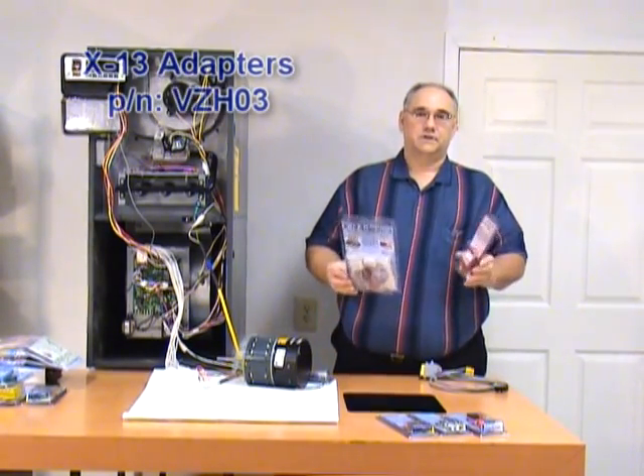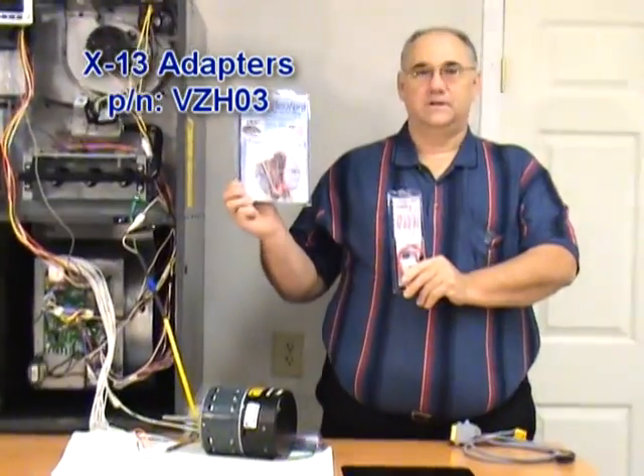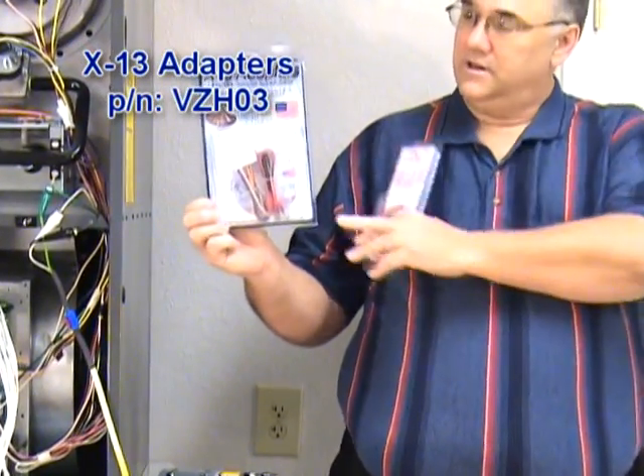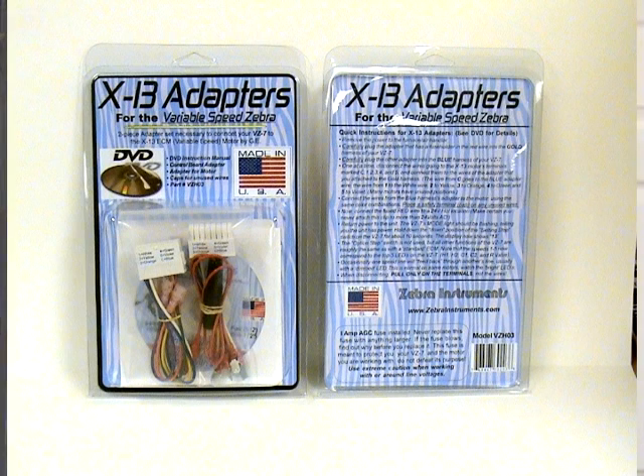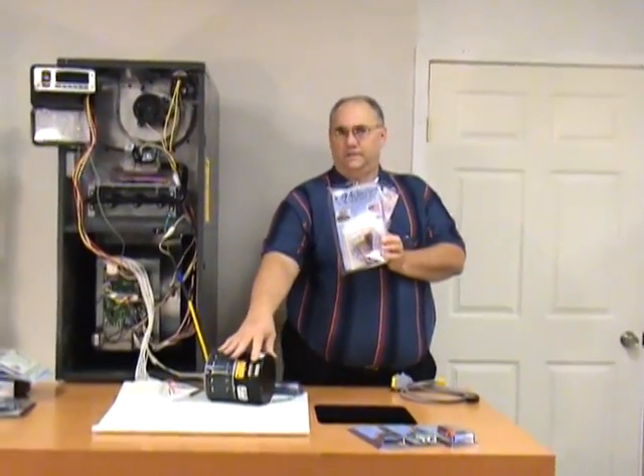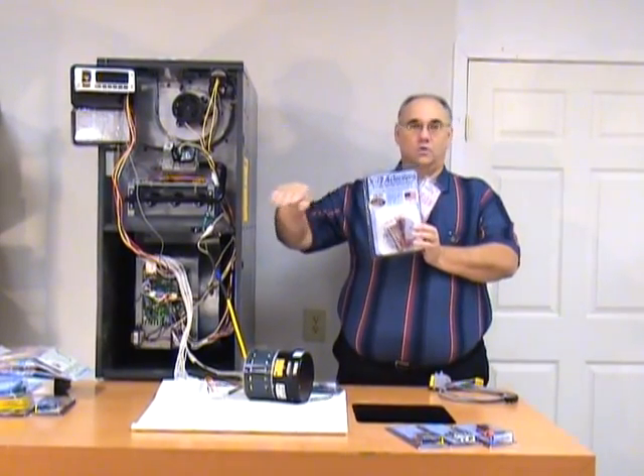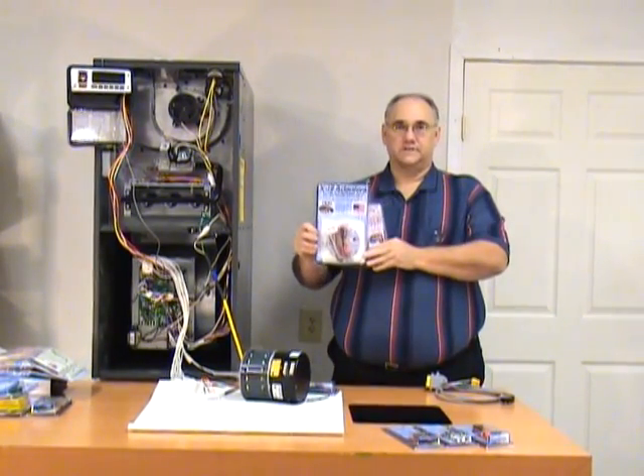The other 2 adapters that are currently made, one of them is for the X13 motor. It's an adapter set with a DVD and instructions. The X13 motors are true variable speed motors, but they have a different connection pattern on them. They have quick connects, all of them in a little white block, instead of a 16-pin low voltage and a 5-pin high voltage like these type of ECM motors have. They use a row of quick connects. And those are called the X13s.